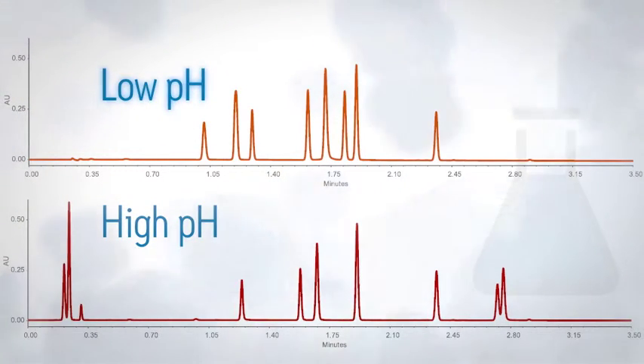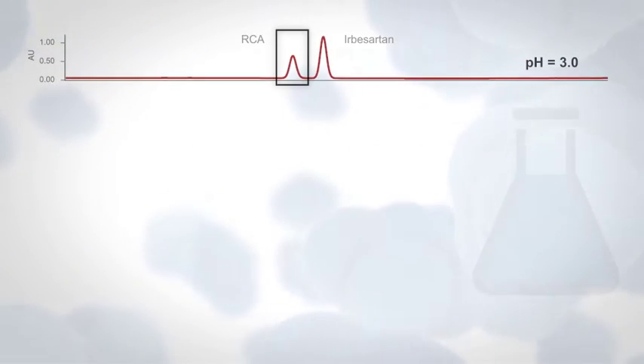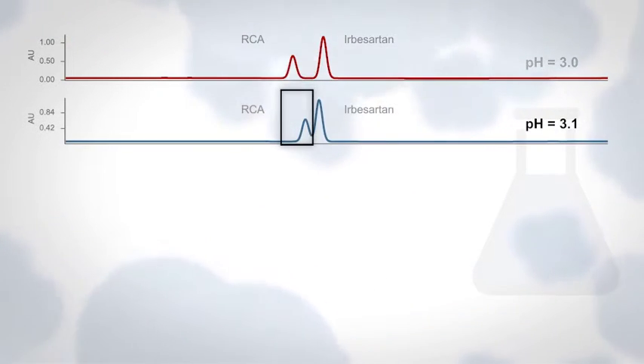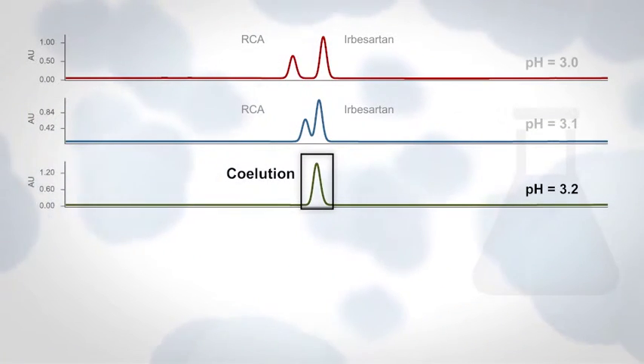However, dramatic changes in selectivity are observed over very small pH ranges. For example, in this reversed phase separation of irbesartan and related compounds, changing the pH using Auto Blend Plus in 0.1 unit increments results in a reversal of peak elution order.